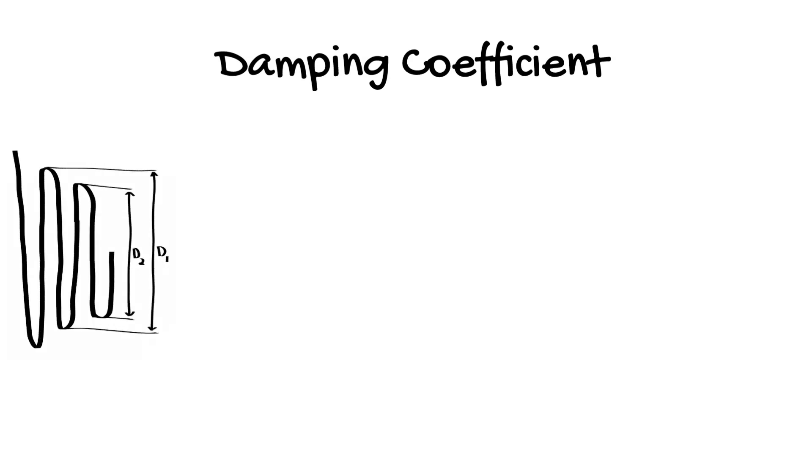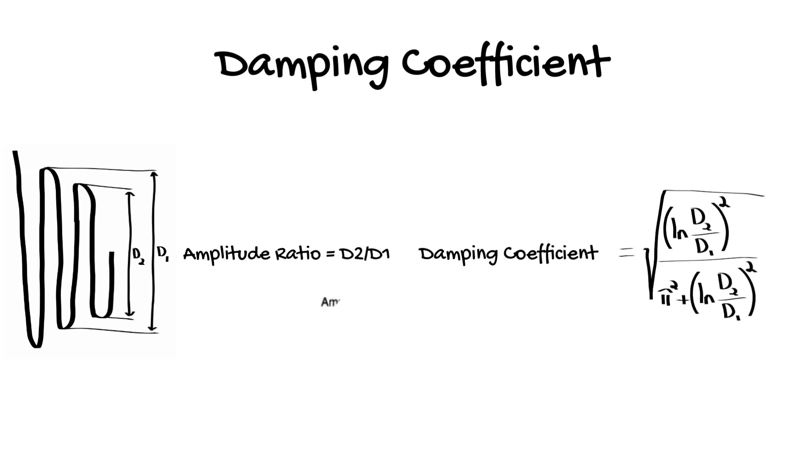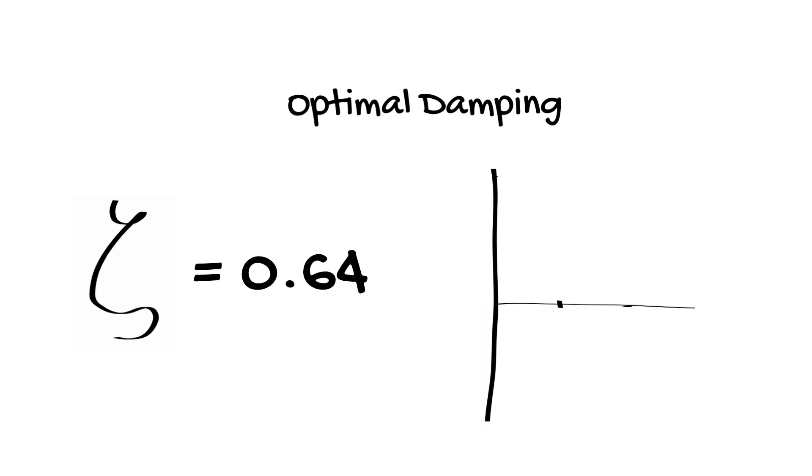If we're going to talk about damping we need to also mention the damping coefficient. This numerically represents the amount of damping present in a system. It is calculated using the ratio of consecutive amplitudes and some fancy maths, although it can also be looked up on a reference table. The optimal amount of damping occurs with a damping coefficient of 0.64. This preserves the frequency responsiveness of the system to react to the next heartbeat without allowing excessive oscillation.